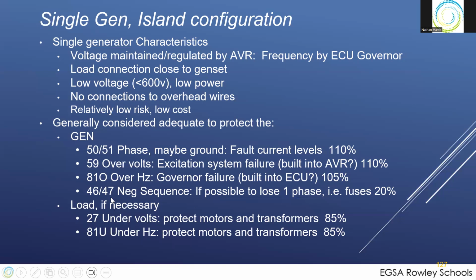You probably have an engine over speed setting that might be at the same level or maybe a little bit lower, so be careful of your engine over speed setting. The 46-47 negative sequence voltage and current, if it's possible to lose a phase, like you've got fuses in a system, set at about 20%, you'll be okay.